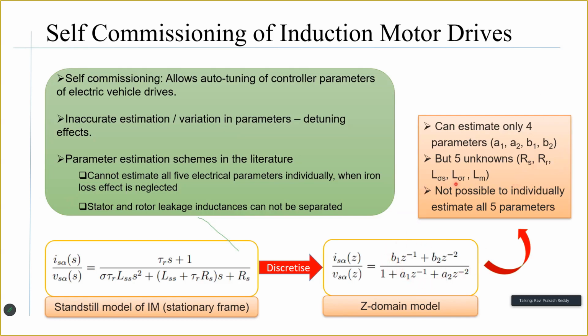However, there are 5 parameters that need to be estimated: the stator resistance, the rotor resistance, stator and rotor leakage inductances, and the magnetizing inductance. Therefore, it is practically difficult to estimate all of these 5 parameters, and we can get only 4 out of these 5, and often people assume a relation between stator and rotor leakage inductances. In most cases, we assume them to be equal, and that is how we get the parameters. But if we make such an assumption, the accuracy with which we estimate those parameters is not guaranteed. And therefore, if the parameters are not accurately estimated, we may have to compromise on the performance of the high performance control schemes that we employ for any motor drive operation.